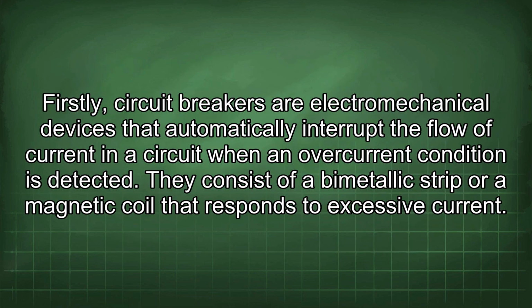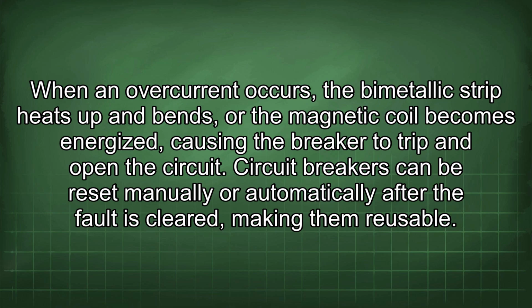Firstly, circuit breakers are electromechanical devices that automatically interrupt the flow of current in a circuit when an overcurrent condition is detected. They consist of a bimetallic strip or a magnetic coil that responds to excessive current. When an overcurrent occurs, the bimetallic strip heats up and bends, or the magnetic coil becomes energized, causing the breaker to trip and open the circuit. Circuit breakers can be reset manually or automatically after the fault is cleared, making them reusable.